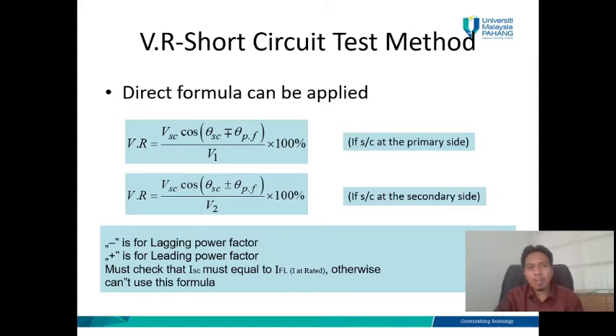Next step is using the short circuit test method. We can use this formula if I short circuit is equal to I full load, so we must test first: I full load is equal to I short circuit. If the short circuit test is at the primary side, we must use Vsc over V1. If the short circuit test is at the secondary side, use V2.